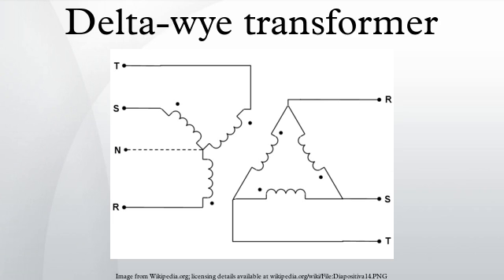The delta winding allows third harmonic currents to circulate within the transformer and prevents third harmonic currents from flowing in the supply line.